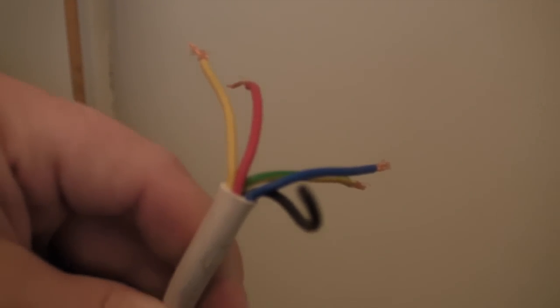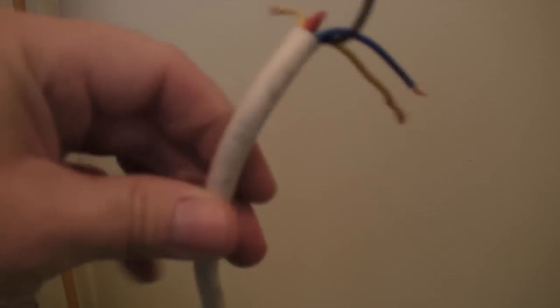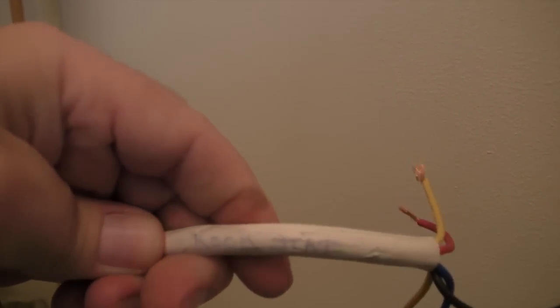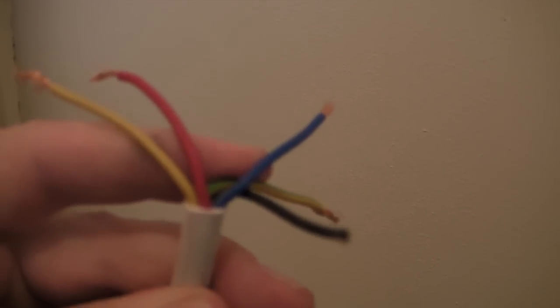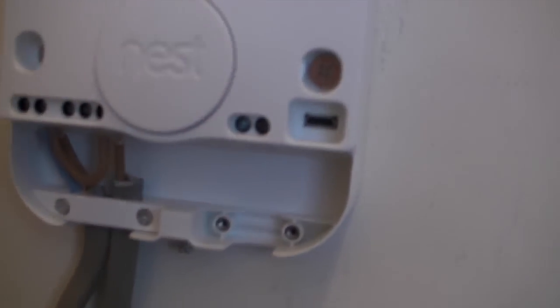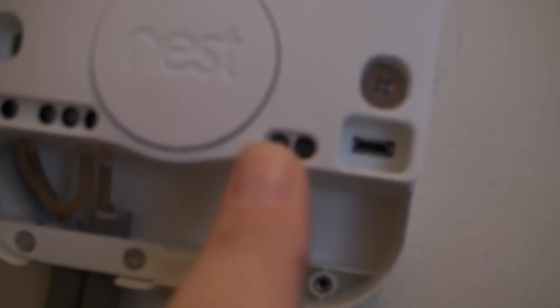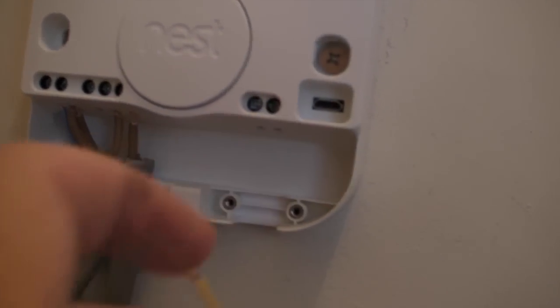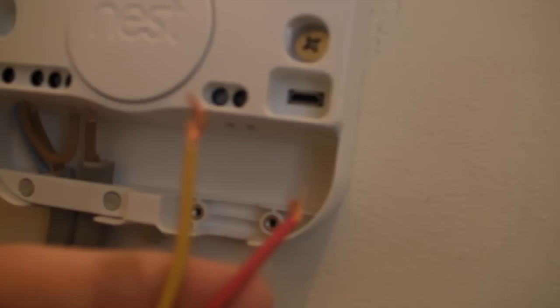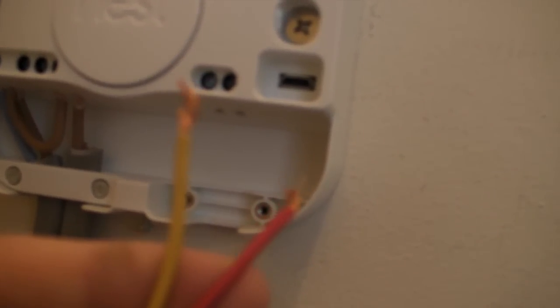Now the last thing you have to do is if you're going into an existing thermostat, is wire this thing in. So here's my wiring from the existing thermostat, I think you see your room stat right there. So what I'm going to do is just use the red and the yellow wire and snip the rest off, and then go into here, terminal one, T1, and T2. So I'm going to go red to T1 and yellow to T2, and I'll show you how you wire it into the other one.